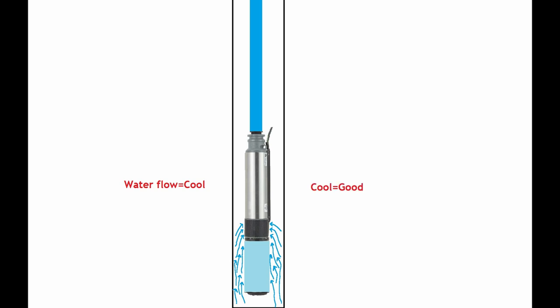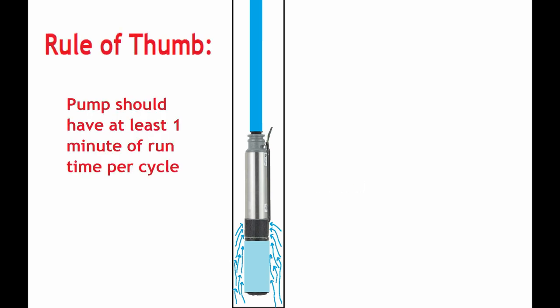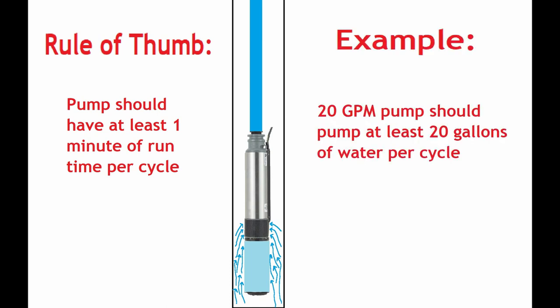The rule of thumb is you want the pump to run for at least one minute per cycle. Meaning if you have a 20 gallon per minute pump, you want the pump to pump at least 20 gallons of water per cycle.